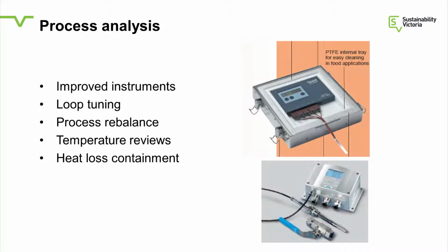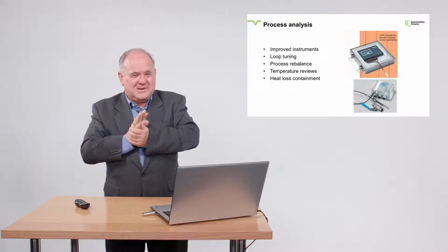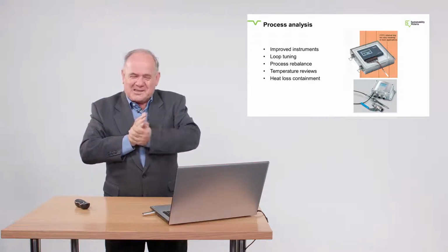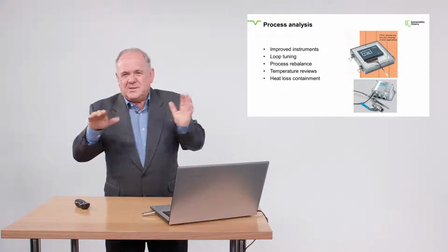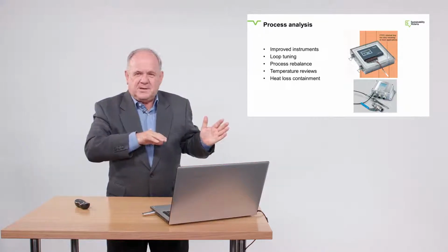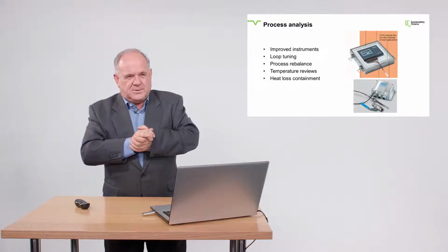So you insert it into the pies, send it through, and you take the instrument out at the other end, and you can see the actual profile that has occurred. Then you can adjust the burners and send the insulated instrument back through the oven. Much better than feeding thermocouples right through the oven and jamming up the oven. It just goes through. Hopefully it doesn't fry the instrument. If the oven breaks down and the instrument's in the middle, then it's a bit embarrassing. But they are a great instrument for fine tuning. Obviously you get better product, you save energy, and it's quite a simple thing to do these days.